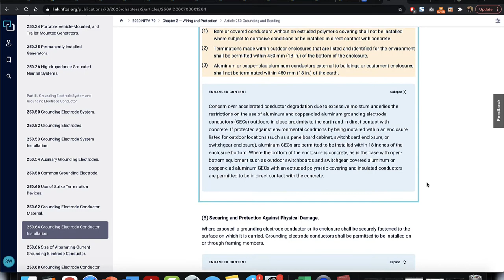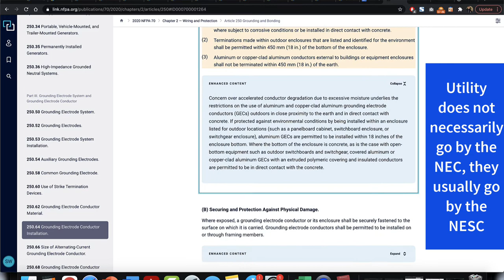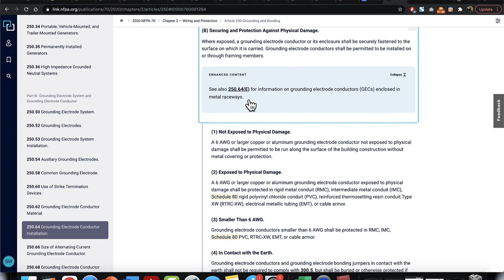And so even though the National Electrical Code has information about when you have a grounding electrode conductor, how you would connect it, it doesn't necessarily mandate that those circuits have grounding electrode conductors. And so only if you have a grounded circuit would you have a grounding electrode conductor. That is dictated by the utility first. So we go to the utility first, get the requirements, and then we open up the NEC and say, okay, the utility requires a grounding connection here. Therefore, we need a grounding electrode conductor, because a grounding electrode conductor takes it from the grounding point on the system to earth. And so that's the vehicle, if you will, to get it to earth.